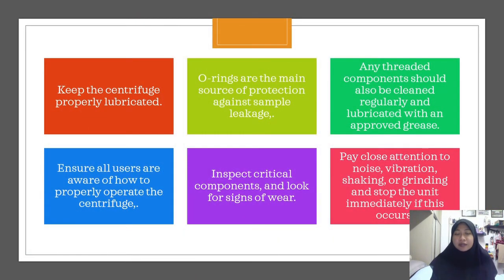These are a few things that can be done. First thing is to keep the centrifuge properly lubricated. The O-rings are an important source of protection against sample leakage. Any threaded component should also be cleaned regularly and lubricated with an approved grease.